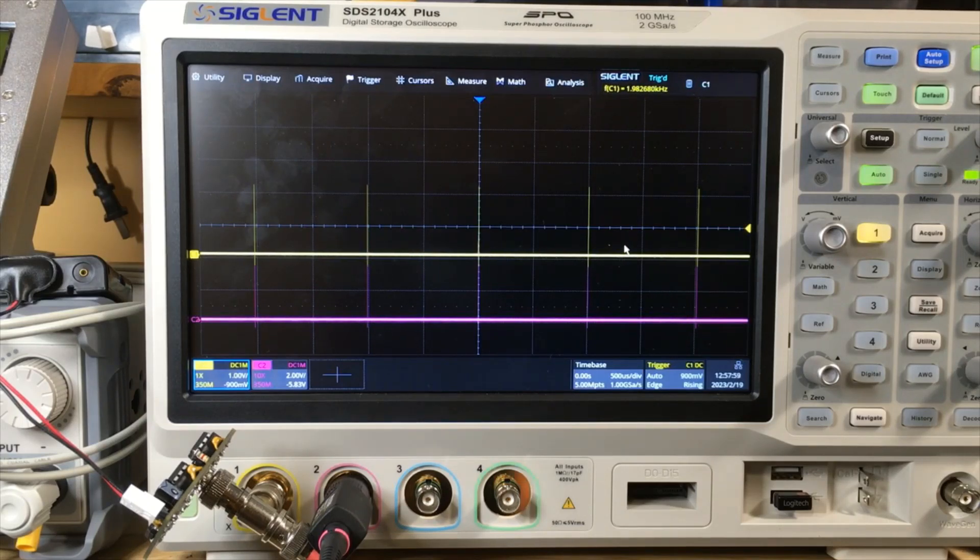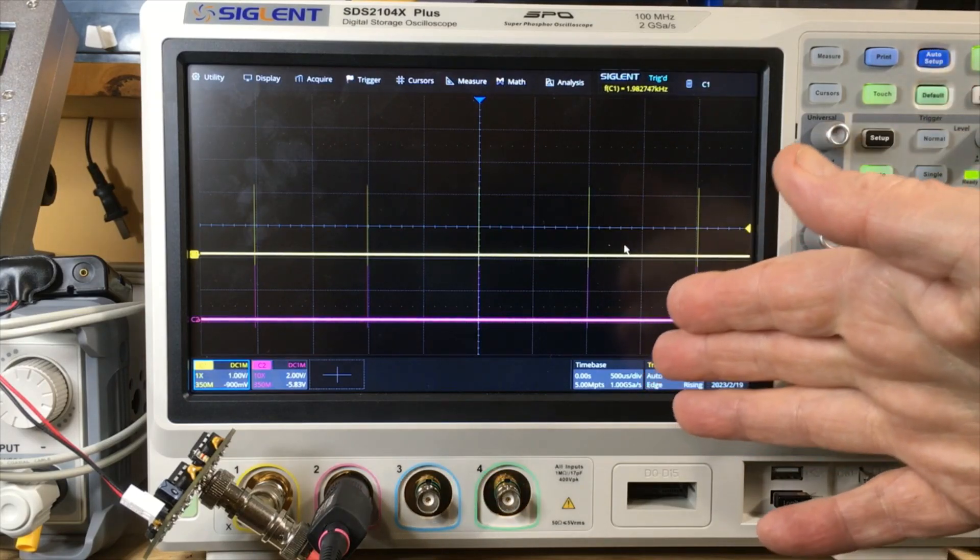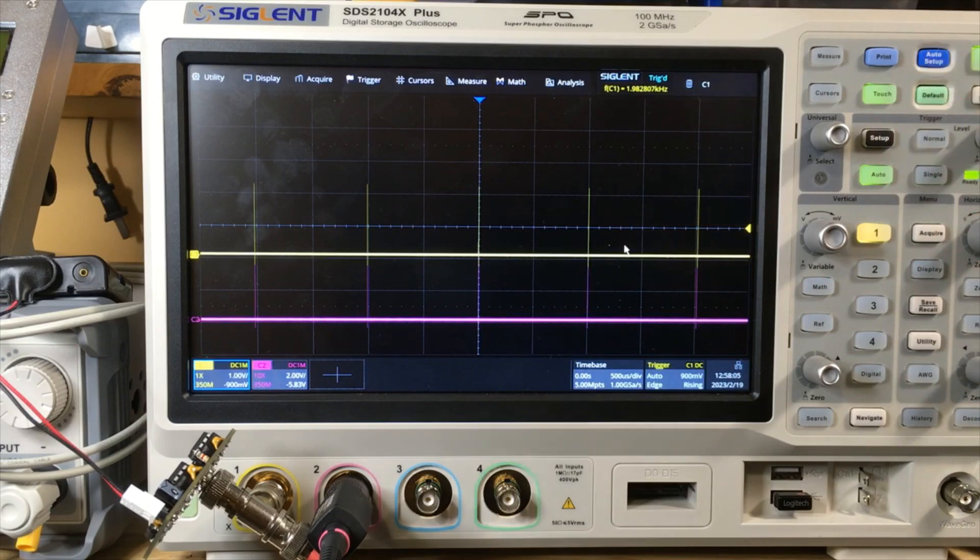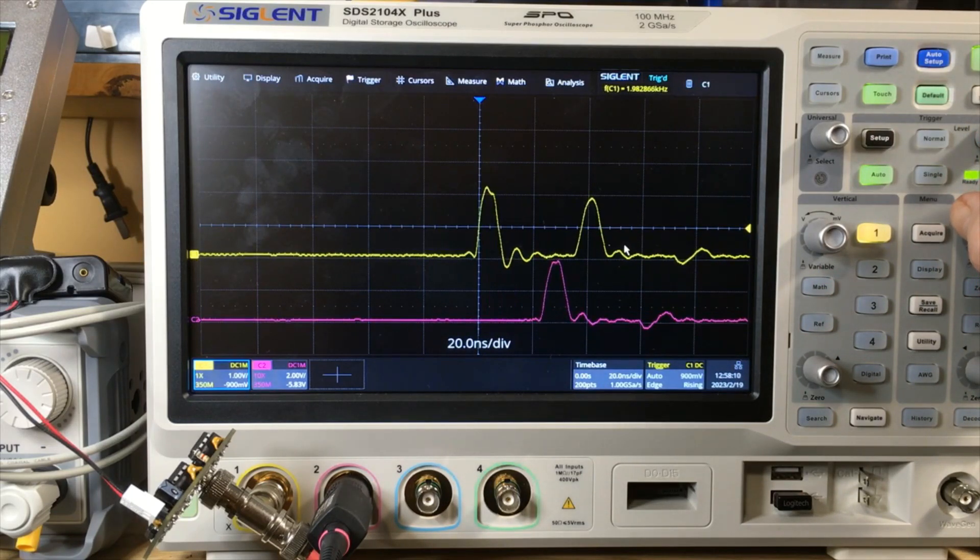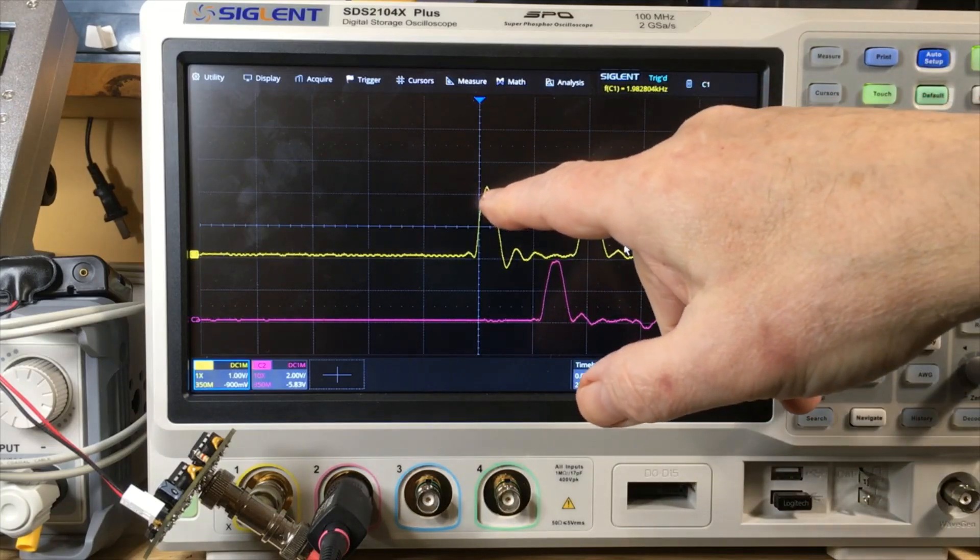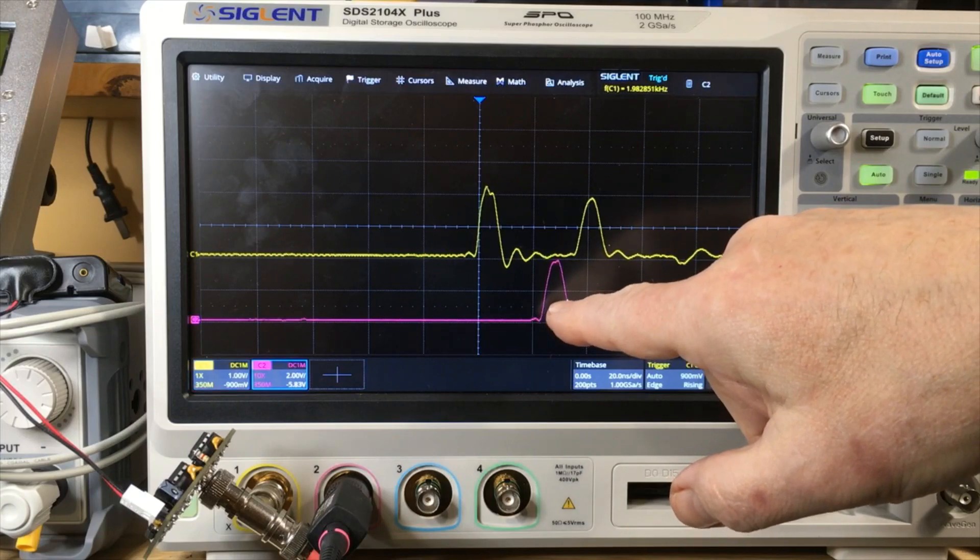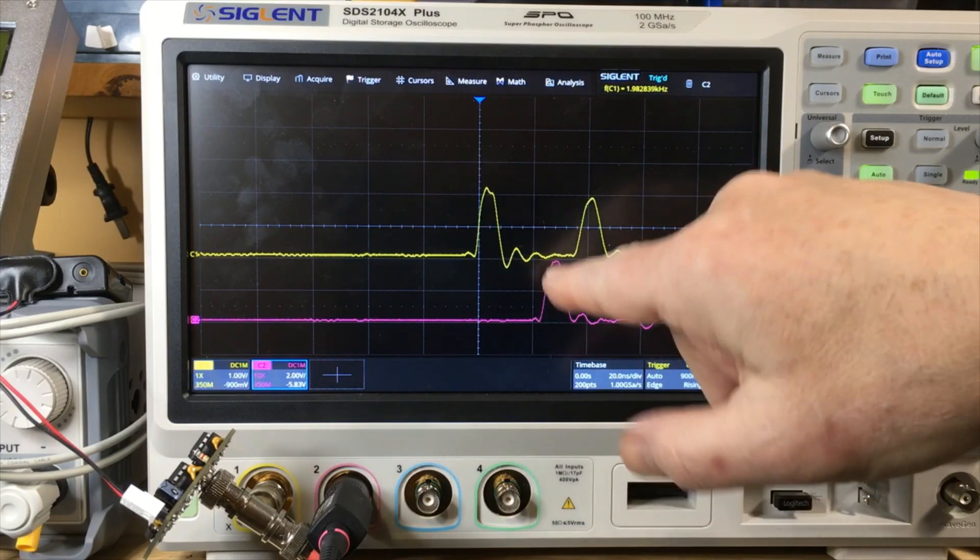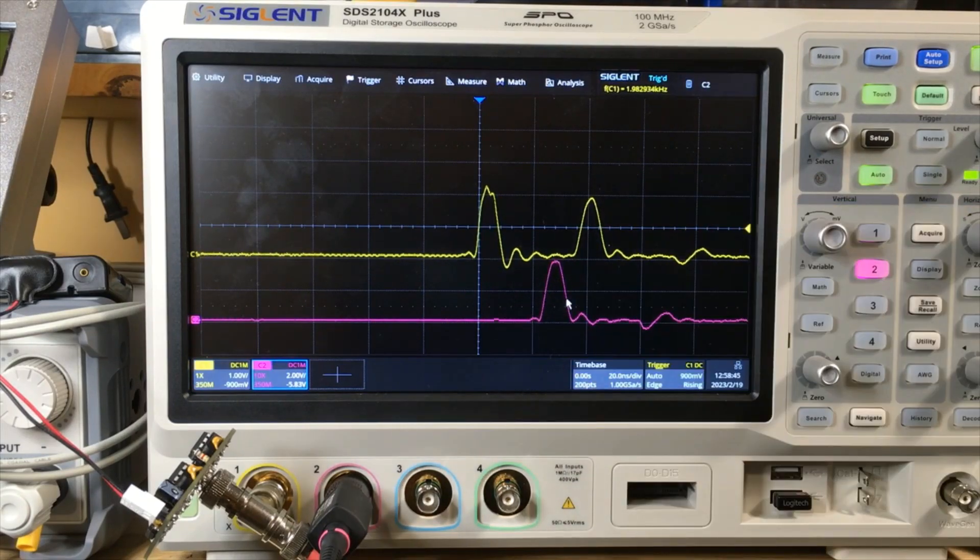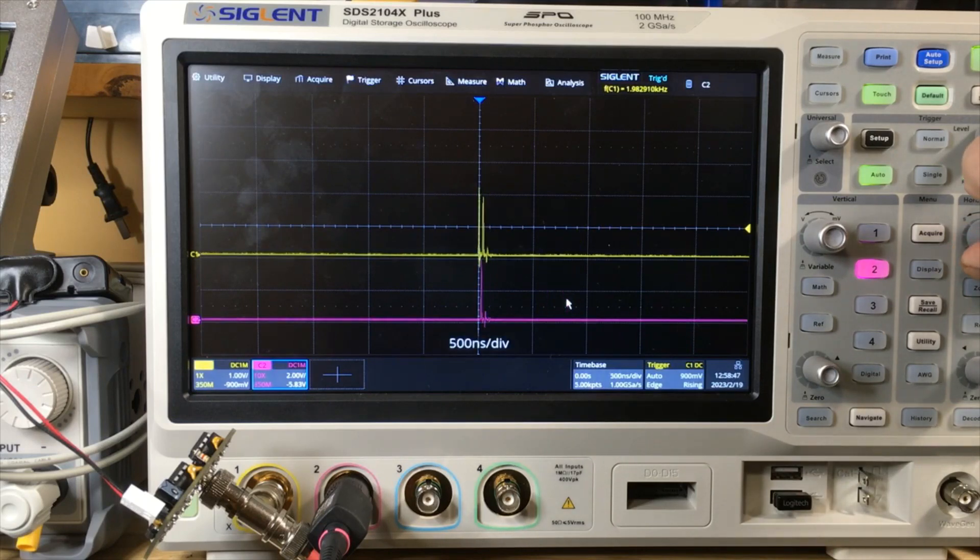We can't see that here right now, so one way you could do it is just change the time base until you can see what you want. Now we have the initial pulse, the reflection, and here's channel two picking up the pulse down at the end of the cable.